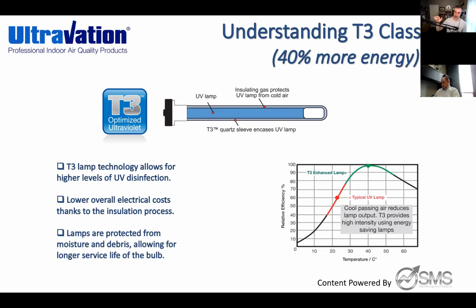If you're using our products that have T3, this is a patented design. We took a standard UV bulb, encapsulated it in a quartz sleeve with some gas between the two layers. Why? It insulates the bulb. Most UV bulbs, especially when you're running your cooling system, can't get hot enough—they can't reach their maximum potency and potential. This bottom graph here shows a typical UV lamp in red. If I really want to get up to that peak performance and get as much potency out of that bulb, I need to keep it insulated. That's why we designed, engineered, and patented the T3 bulb—I can get that maximum 100% potential out of my UV bulb because it's insulated, it's protected, it can hit hotter temperatures, and the cooling air going by isn't affecting its performance.